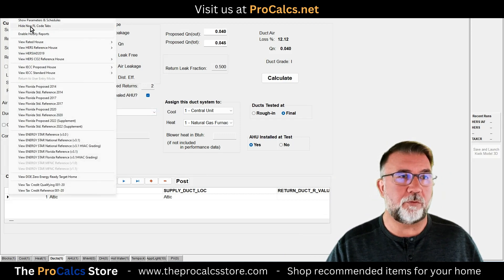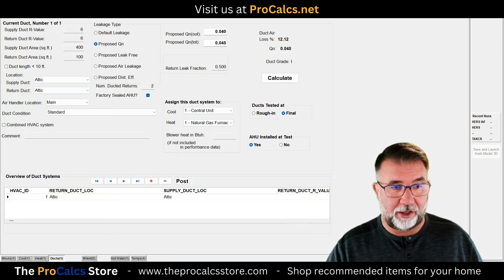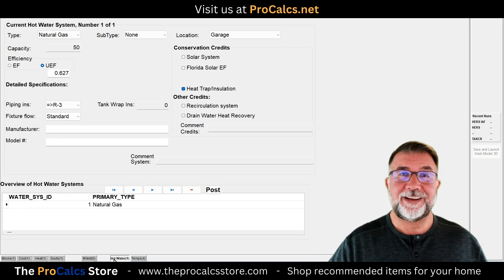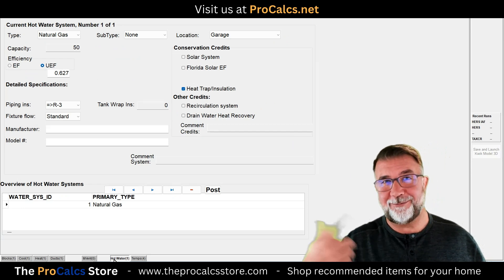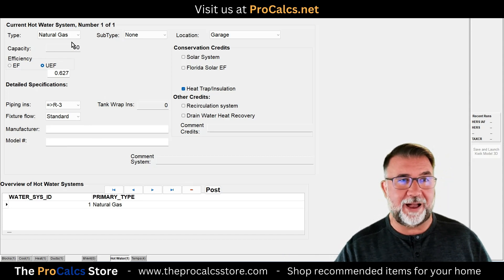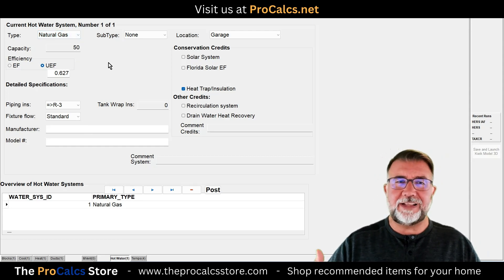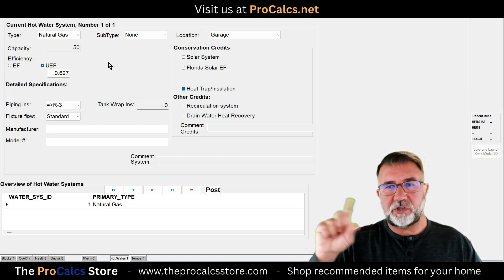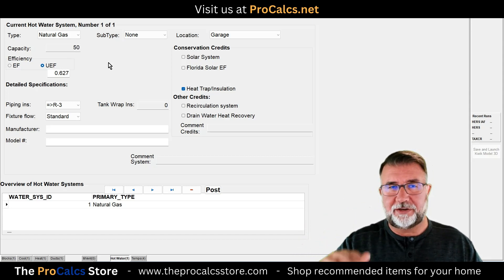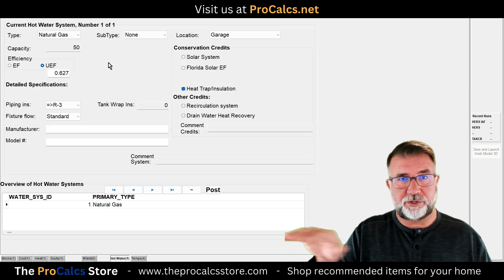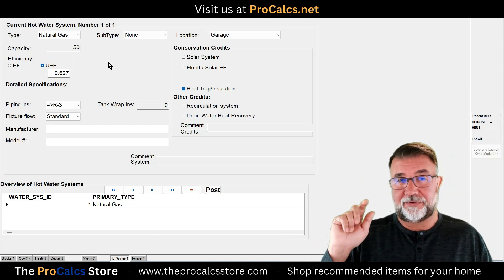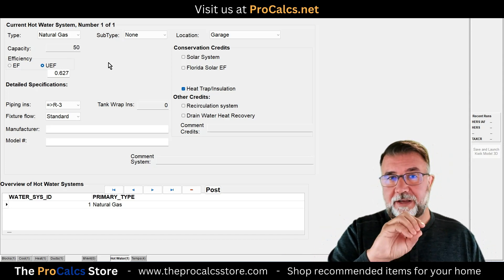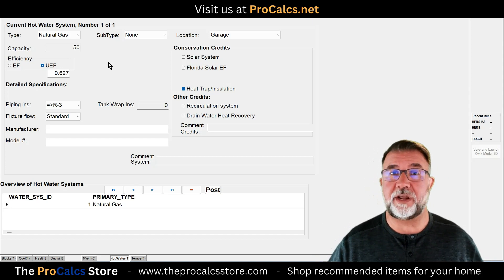We've had situations where testers call us on-site saying the duct leakage came in at 0.05 but our calculation shows 0.045 — we change it, recalculate, and confirm the energy calculation still passes. In Energy Gauge you can view and remove non-Florida tabs. The water heater section — and note that it's a water heater, not a hot water heater, since cold water goes in and gets heated — lets you enter capacity and fuel type such as natural gas.